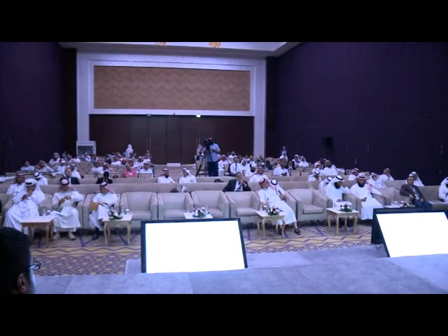This is mostly used in the control center once we have an interface between, let's say, transmission and distribution. Limitation of access is issued for work in the vicinity of live high voltage apparatus. And the hotline work, which is issued for work on a live overhead line. Finally, the PEA, portable earth application, used once we have to apply a portable earth when we don't have a CME, circuit main earth, available. This is mostly used with outdoor equipment or old outdoor equipment.